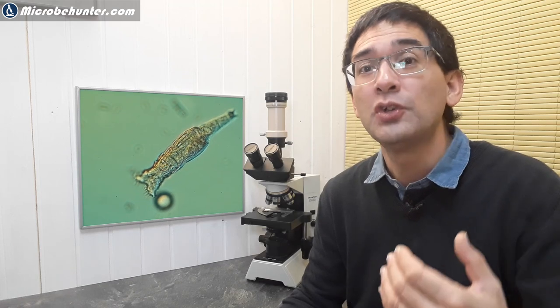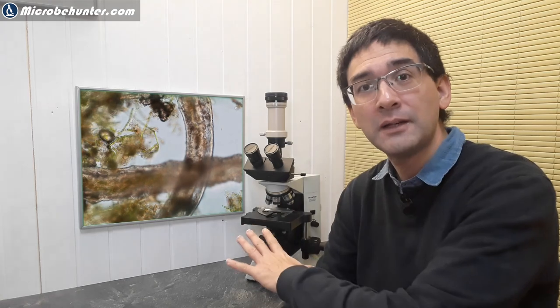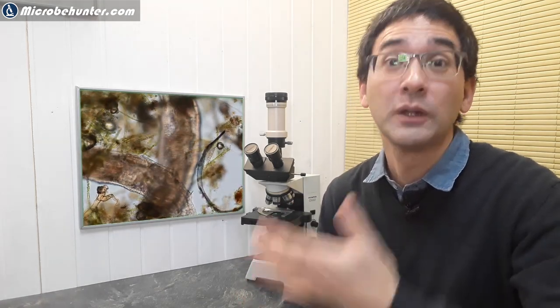So what is the cutoff? I would say that essentially five megapixels is perfectly fine. Even three megapixels is going to work. However, what you want is to capture the full image resolution with a microscope camera without any loss. This depends of course a little bit on the magnification as well, but with five megapixels you can capture the full image resolution that the microscope provides. Everything more than that is waste. Everything significantly less than that, then the camera will capture less of the image resolution that the microscope delivers.